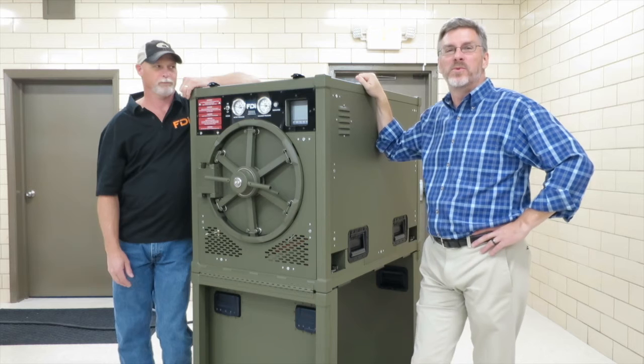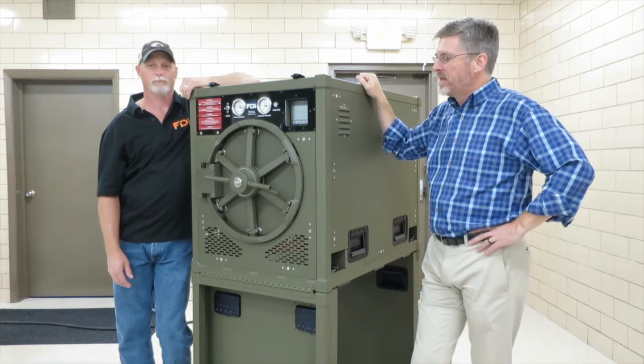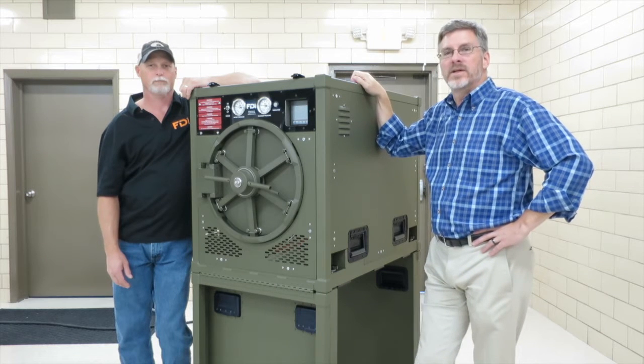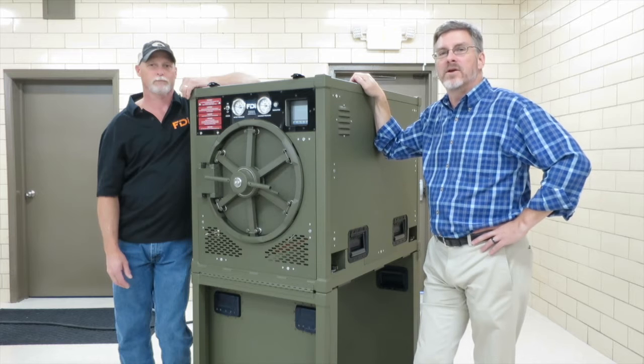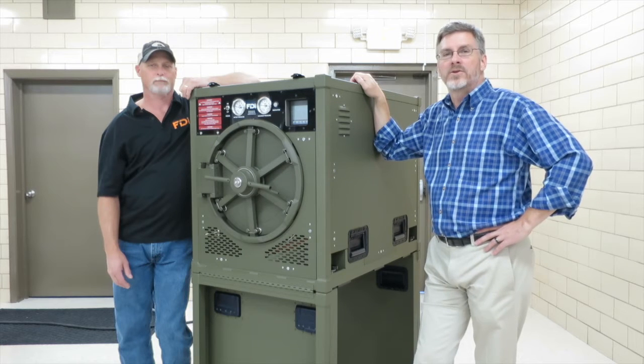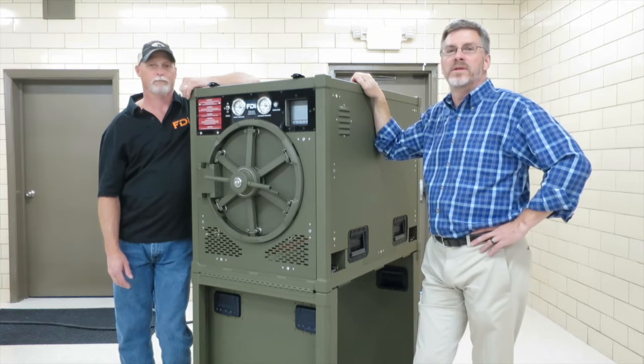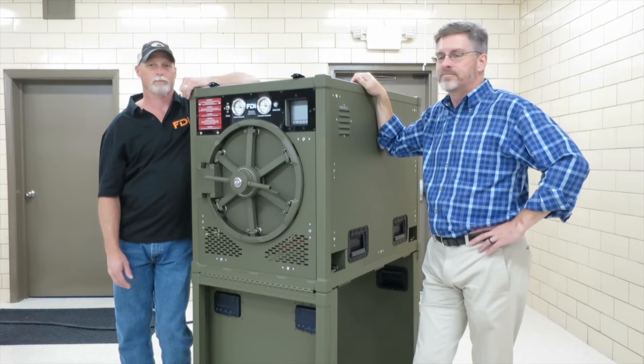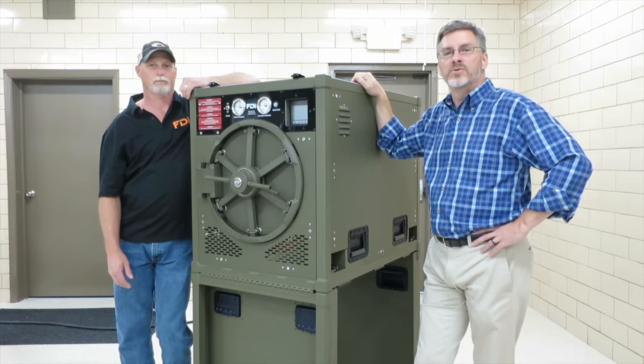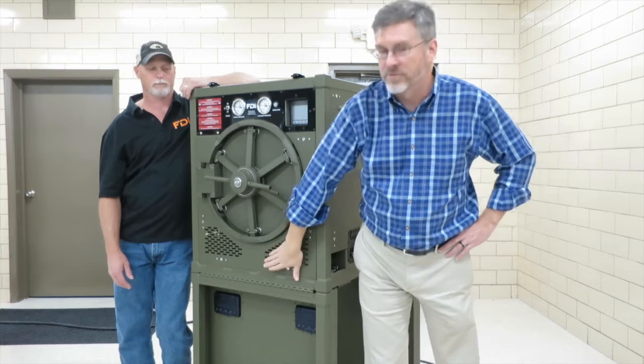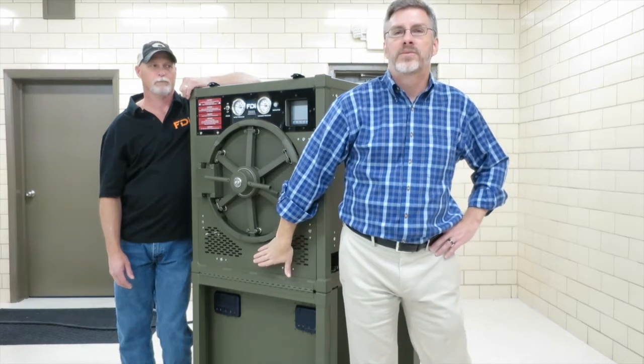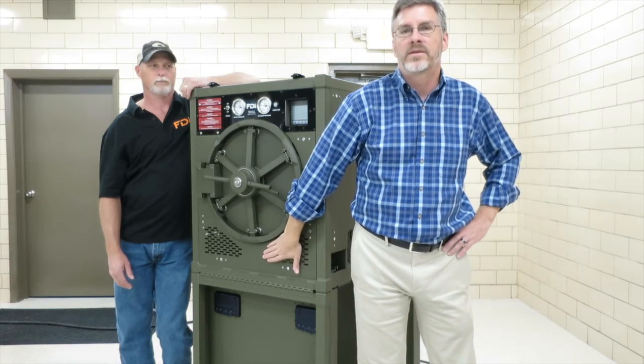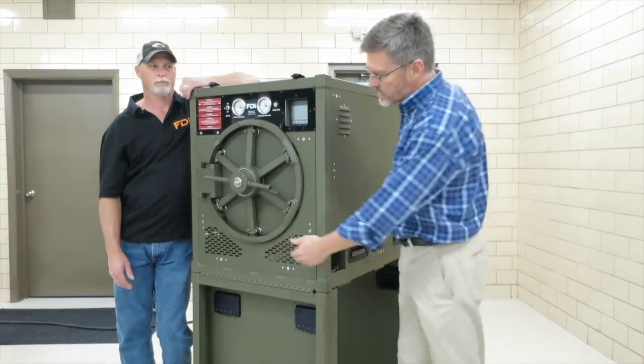We're here with a P2131 steam sterilizer, and today we're going to replace the RTD probe. The RTD probe is the temperature probe that controls the sterilizer during exposure. It's located in the front. It's actually measuring the temperature in the drain of the chamber. So it's located here.